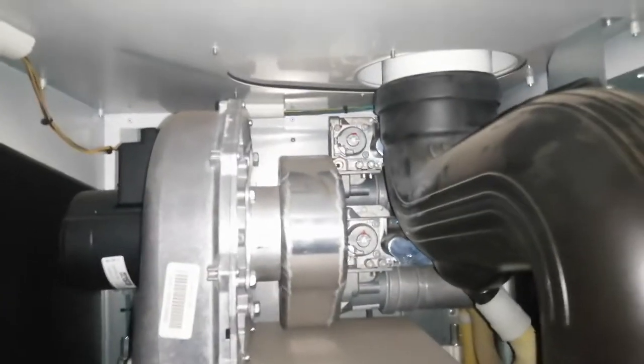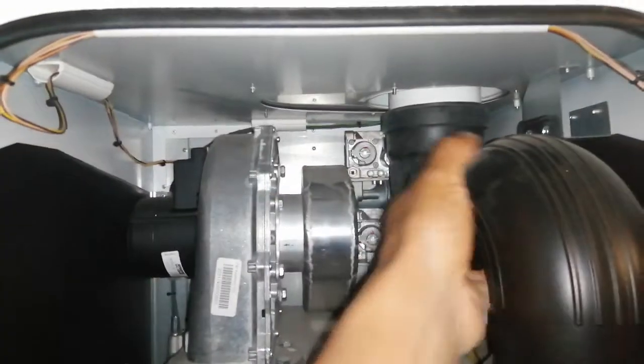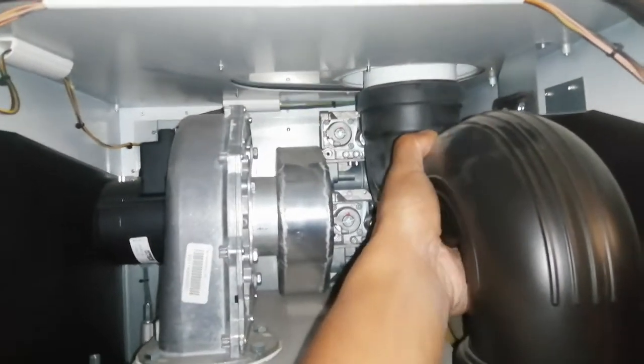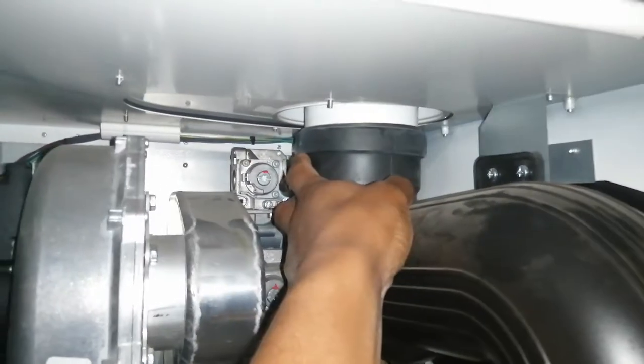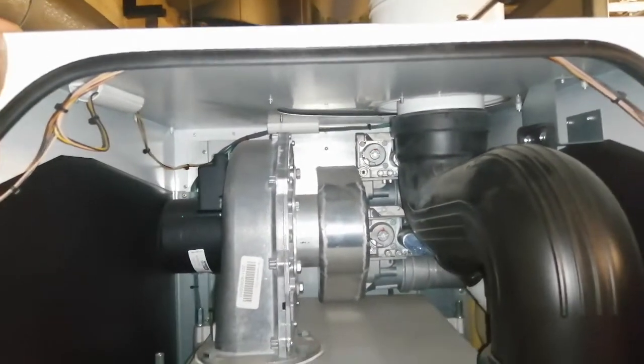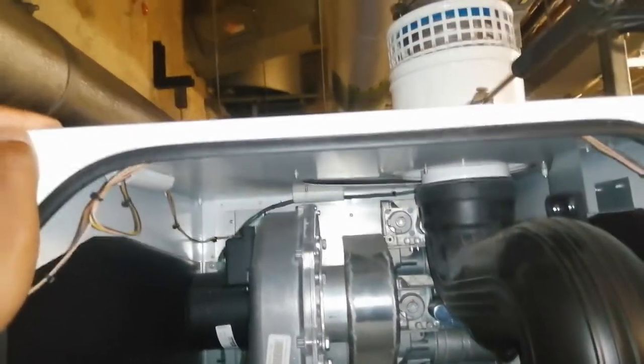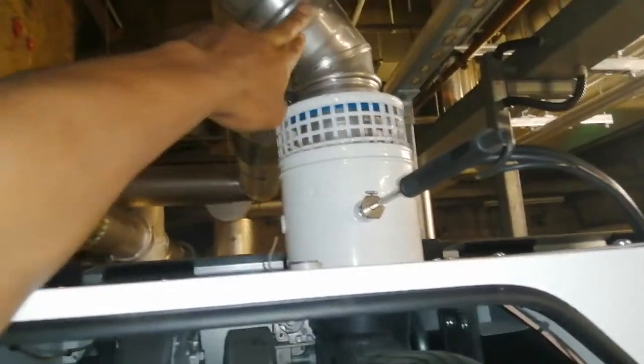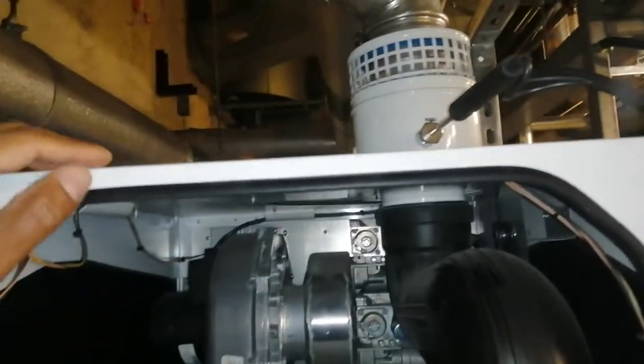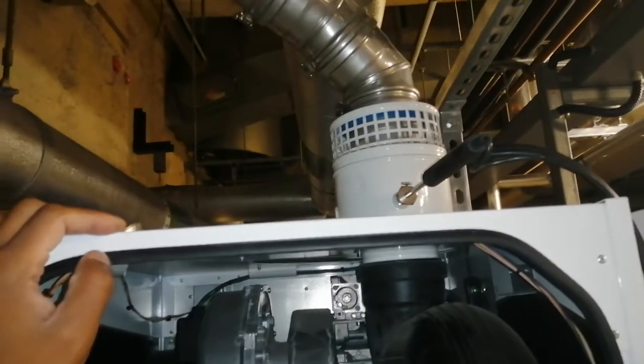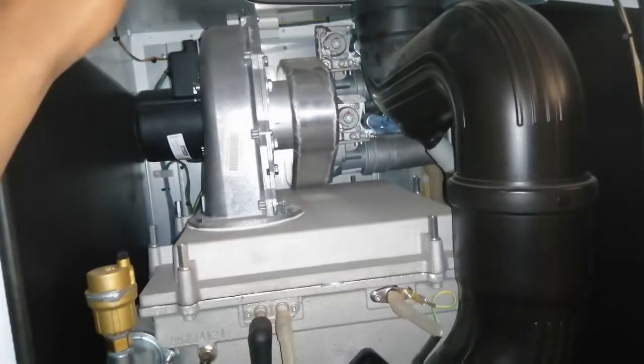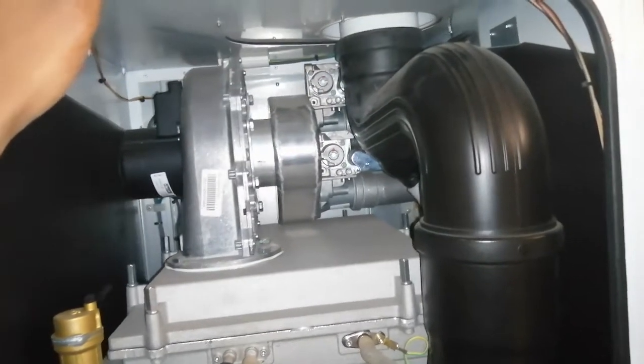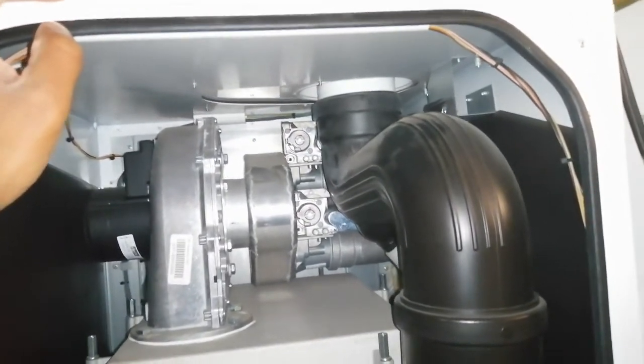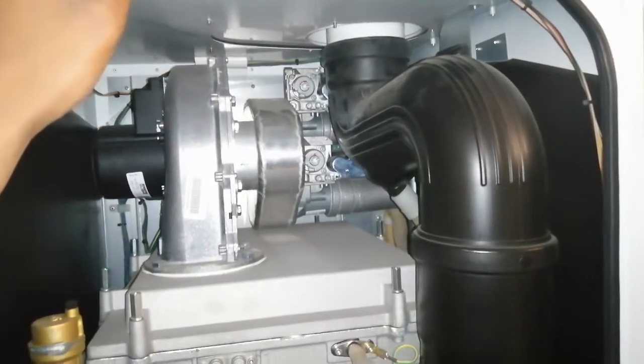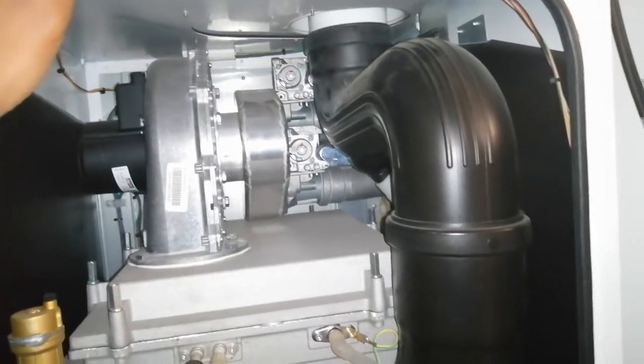You also want to check your flue. Sometimes on some of these you can just give them a little tug to see if they're connected. Make sure it's connected. Have a visual check of your flues, and sometimes you do need to give them a little tug to make sure that they're secure. Ensure that they're also clipped throughout their run. This is an open flued appliance, so a flue flow test will need to be carried out on it once the boilers are hot.